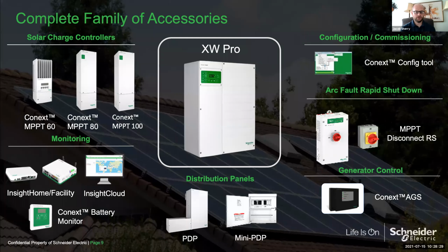Our Conext config tool is a useful tool for saving pre-configured settings files if you want to easily replicate those among other devices within the same family. You can save files in the native format using the config tool, and then update them and upload them easily to subsequent devices. You can also use it for AC output voltage calibration in multi-unit systems, which is a very nice feature as well. We do have full code compliance through our MPPT disconnect RS, which offers both arc fault and rapid shutdown compliance.